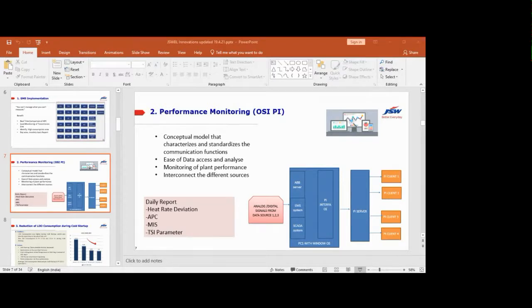With the help of this data, we are generating different reports, like the heat rate deviation. All unit parameters, MS temperature, MS pressure, reheater temperature, vacuum, all the parameters are collected at a single platform, and you can compare unit to unit, phase to phase. So anytime comparison can be done with this Pi system. Auxiliary power consumption we can compare, MIS report generation, and a turbine health monitoring system is also implemented here. It's a conceptual model to standardize the communication function, ease data access, and analyze monitoring of plant performance, interconnecting the different sources.